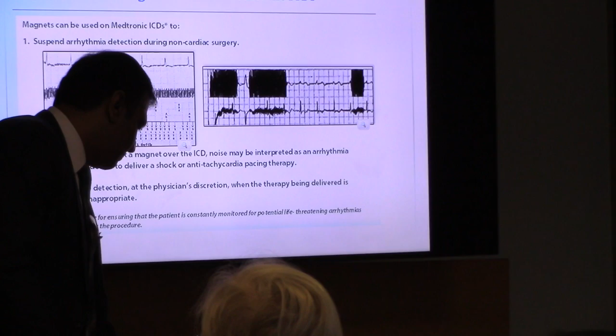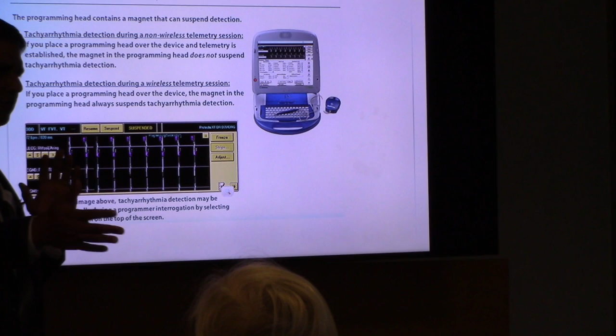All right. So when you put the magnet on an ICD, this is what you can see on the programmer screen. It would say suspended, meaning that all these therapies are suspended. I don't know how many of you have looked at a Medtronic programmer screen. Have you ever? If you look at the programmer screen, on the top left, we always have the mode the patient is set at, and then you would have whatever therapies are turned on. So in this case, VF therapies are on, FVT or fast VT therapies are on, and the VT zone therapies are on. Okay, so this means all three. So if there's somebody coming in to check your device, this is what we would look at first. Make sure that these three are on, because your ICD patients have to have those therapies on.